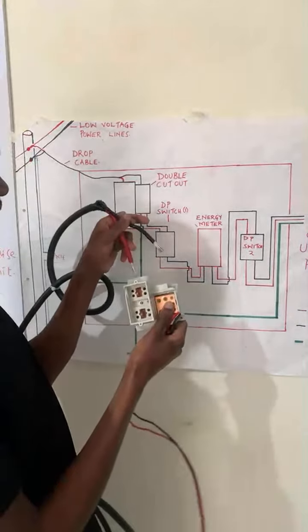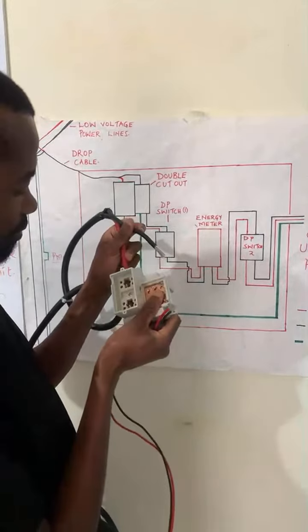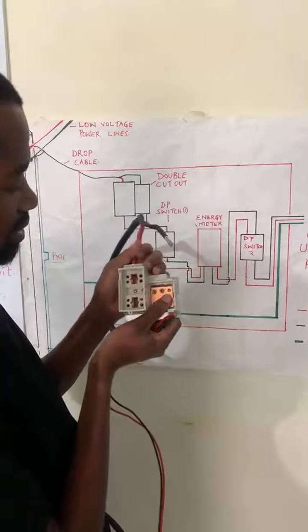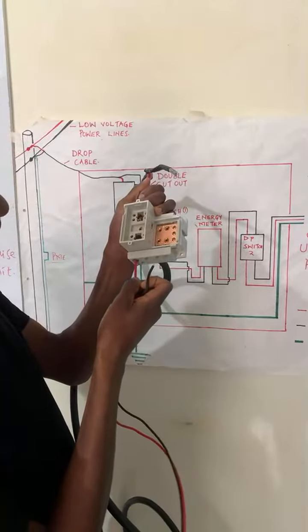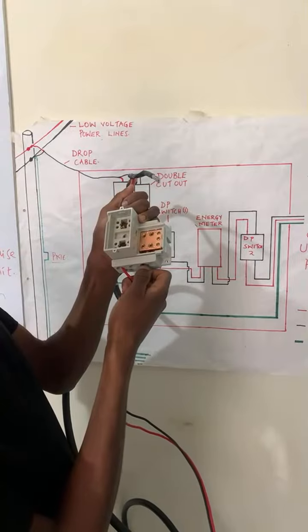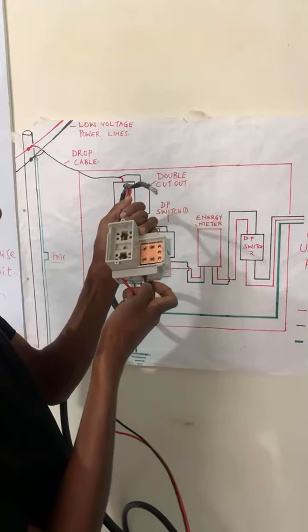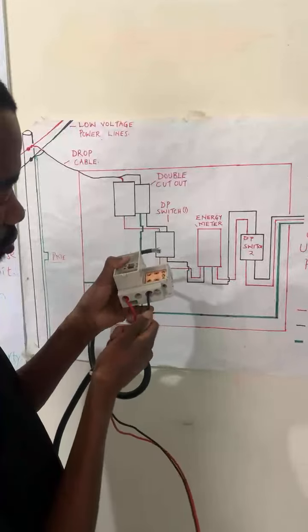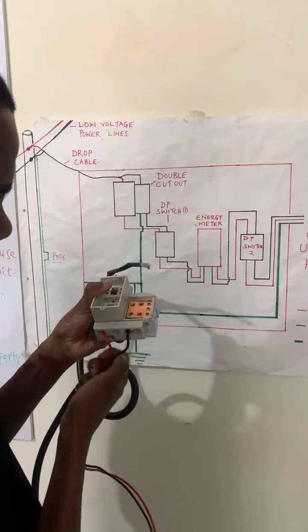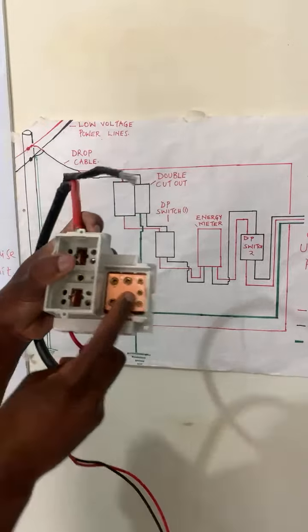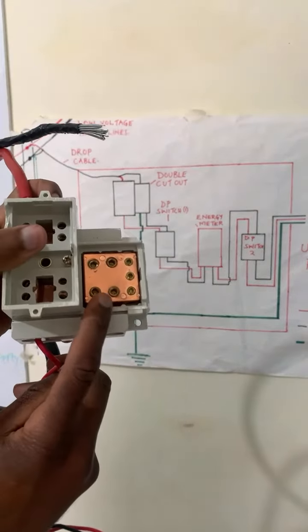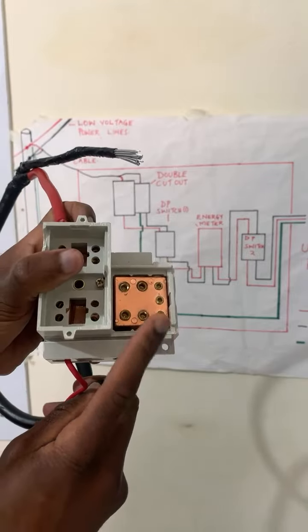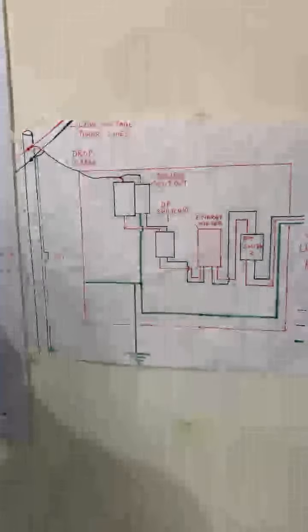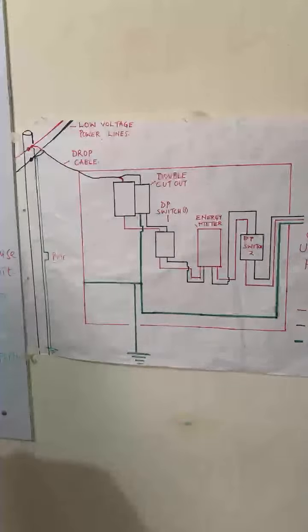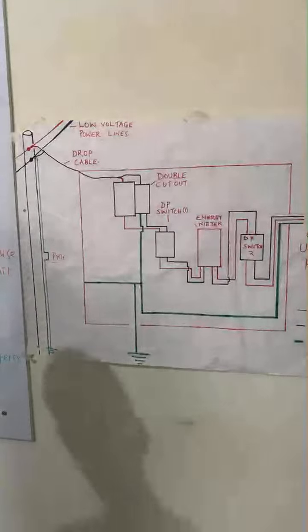So at this red here, which is coming to this point, as well as the neutral coming in here, we'll then have our red connected there and our neutral connected here. Okay, so we will do a double connection whereby we have the neutral connected there and also tap the earth from this plate. So this plate will give out an output for the neutral as well as the earth connection. That is how bonding is done. All right, so that is how we do the bonding.